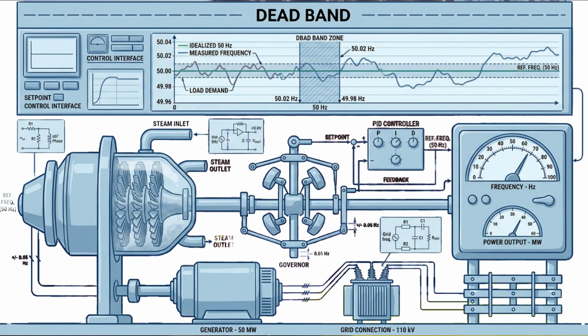So anyway, as all that is happening, Nicholas had asked, so what is happening on the side of generation? Now it has gone out of the dead band. The generators have a governor system, a speed control system. It tries to pull the machine back to its normal speed. So it was at 150, it has gone to 180, it's rising. It tries to pull the machine back to its normal speed of 150 by reducing the amount of water that is hitting the machine. So controlling the mechanical input.